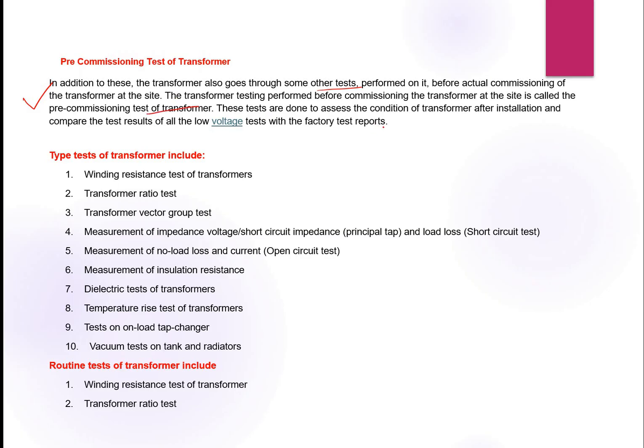These tests are done to assess the condition of the transformer after installation and to compare the test results of all the low voltage tests with the factory test reports. Now we are going to check what all the type tests of the transformer are.